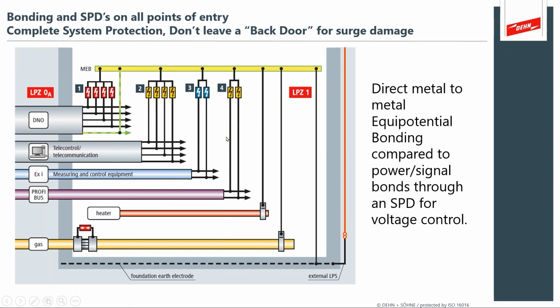And remember, you want to apply surge protection devices on all of these incoming lines and don't leave a back door for surge damage. We've seen lots of applications at places like PV farms where the customer has done excellent work with all of their other aspects, and they've left out, for instance, SPD devices on the low voltage control signals. Well, when that low voltage signal comes back into your critical systems, it will allow a backdoor for surge damage. So that's why we use that term backdoor. Don't allow unprotected wires to come into your critical infrastructure.